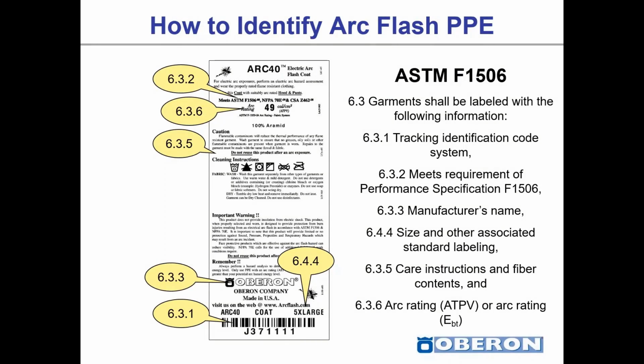How do you identify arc flash PPE? This screenshot shows the label from a typical garment or arc flash hood. The ASTM F1506 standard is the performance standard that manufacturers must follow. It provides guidance and instruction on how to label a garment. I've identified those different points here. It's important to note the arc rating itself, the applicable standards it's in compliance with, the care instructions, so cleaning, and there's even an identification code tracking system. In Oberon's case, we use a barcode and individual serial number.